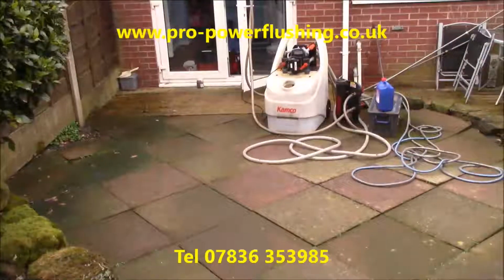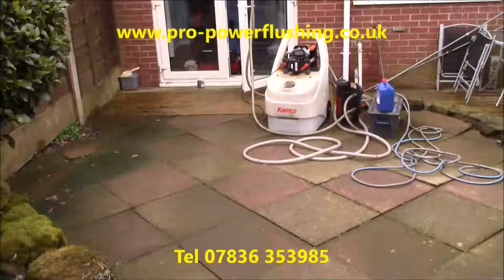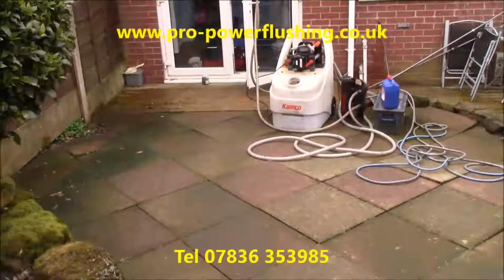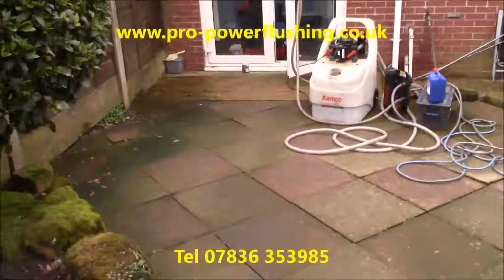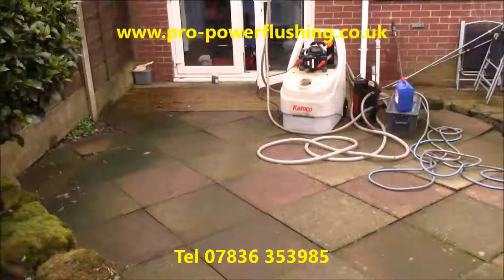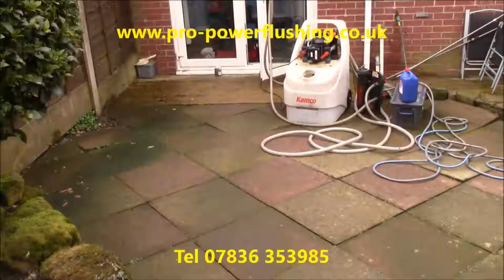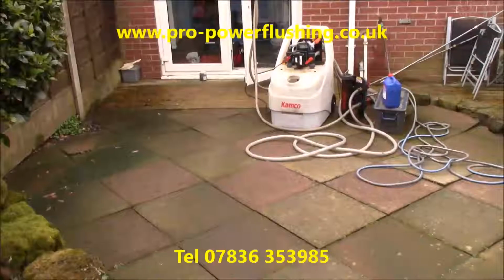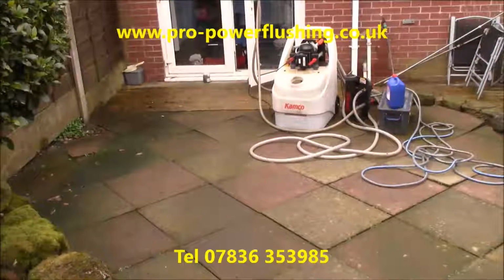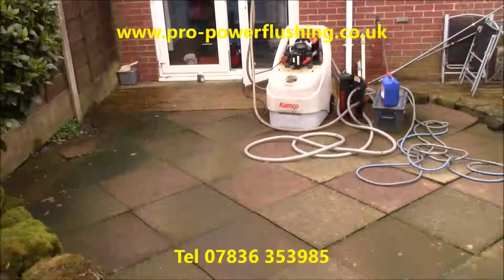It's a Ramara boiler. Not our favourite boilers, but anyway, it is what it is. It seems to be running and putting some heat out. It's just the system's so clogged up that there was no flow getting around at all. So we're hooked in. We've got the Kamco CF210 Titan commercial power flush pump on the go. We've got the magnet hooked up, the Kamco FX2 chemical in there. And we're getting a great flow around the central heating system, so the job's going really well.